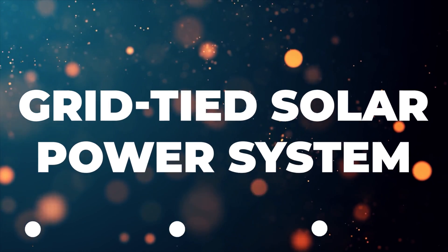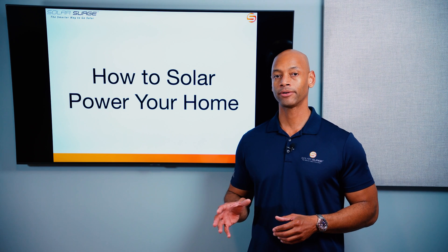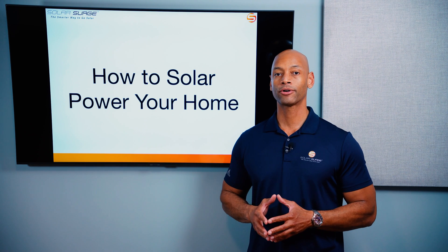The first type and the most popular is what we call the grid-tied solar power system. Solar panels provide power to an inverter, which converts the electricity from direct current to alternating current to match how our homes are wired and how the electric grid is wired. That electricity is fed in parallel with your utility service, so you actually have both power sources activated at the same time. The solar power provides as much power as it can to the house, and if the needs of the house are fully met, any excess solar can be exported back to the power company for credit.